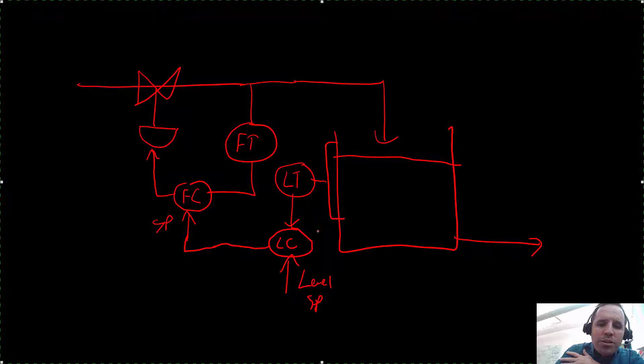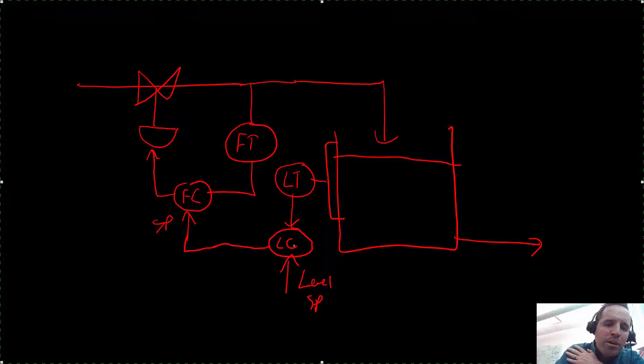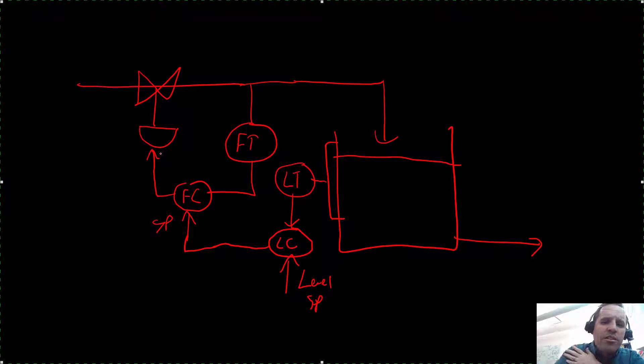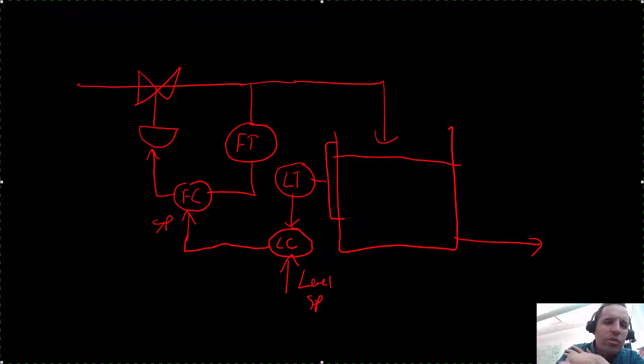This is called cascade control. When we have a master controller — in this case the level controller — that calculates as its manipulated variable the setpoint of another controller, that other controller is known as the slave controller. So the level controller is trying to achieve a certain level and tells the slave flow controller what to do.